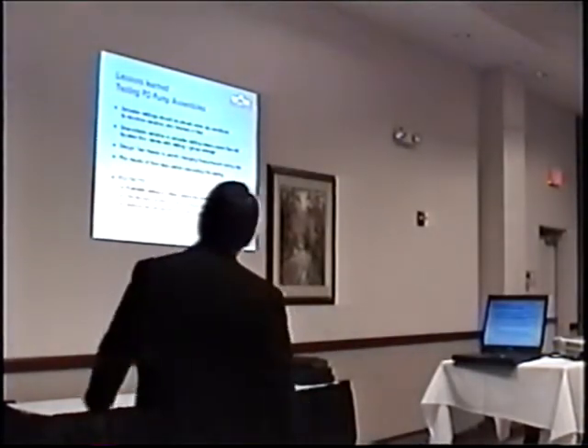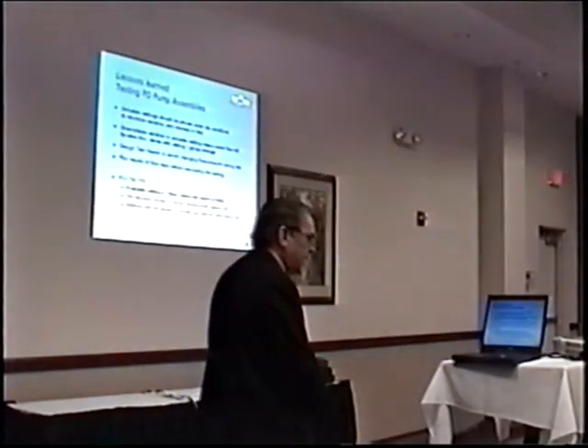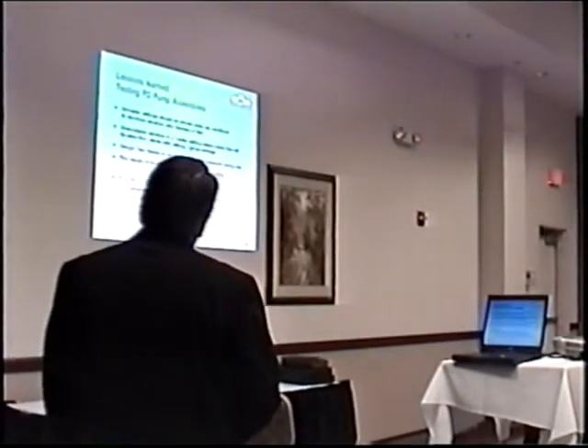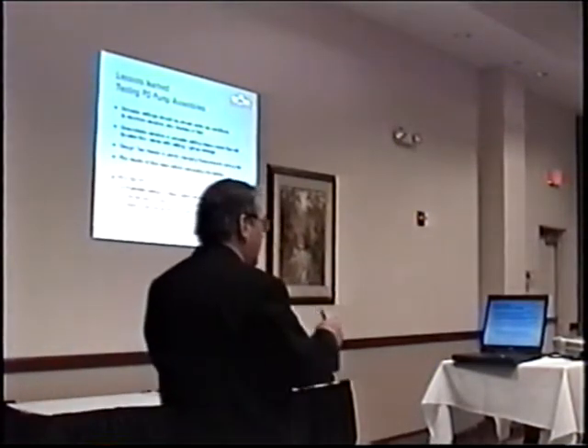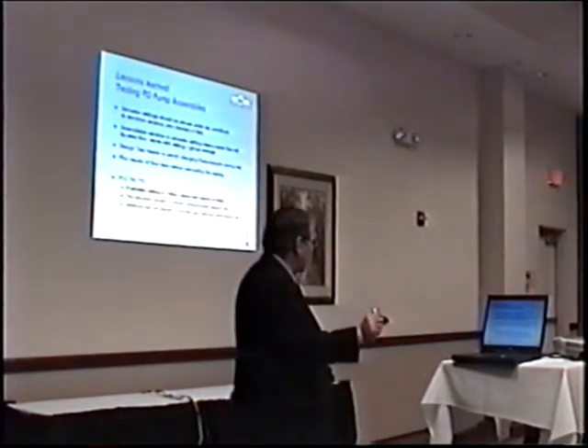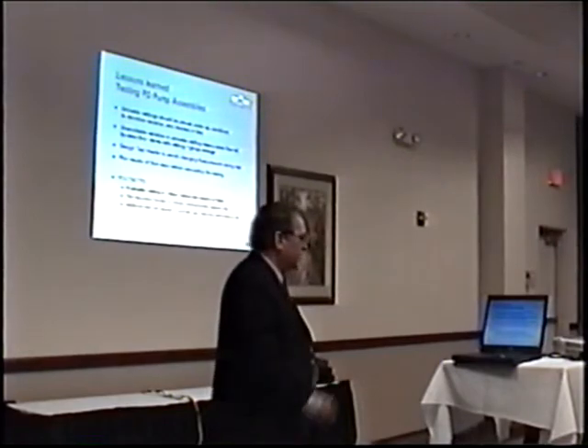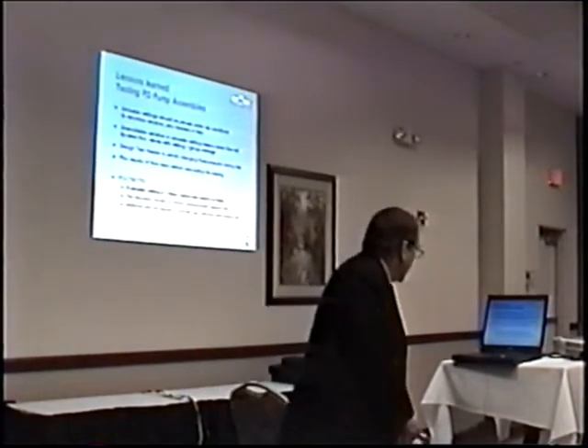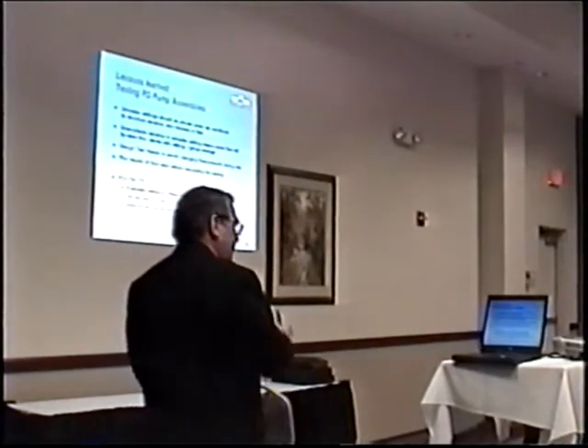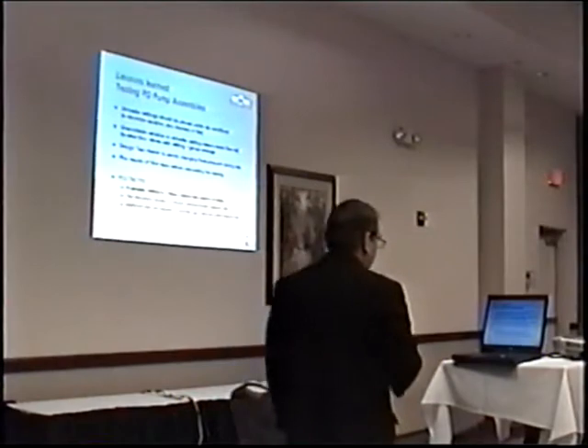Anyway, lesson learned. Unloader settings are tricky. They should be set in a hydraulics lab, and even then, I'm not sure what you're going to get. There's unavoidable variation, so you'll never get a nice pump curve like you do with a centrifugal pump, where you've got the factory line, and you get this nice line just above it usually, and then you feel good about the pump test. You're never going to get there because your unloaders are too sloppy, and you can't test to the max anyway, because your unloaders have to be below that max.